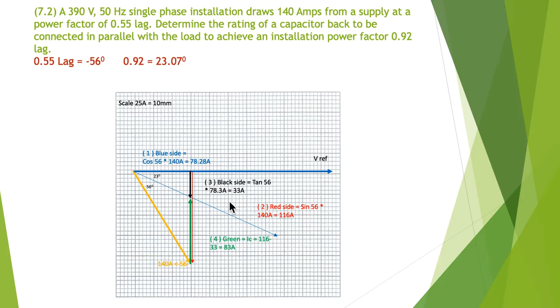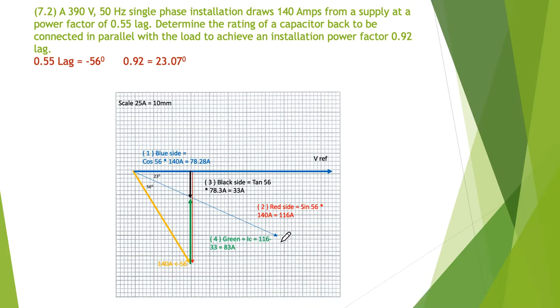I'm subtracting the red and the black to equal the green. Step four: the green one is 116 minus 33, giving me 83 amps. My 83 amps multiplied by my 390 volts for the current in the capacitor.